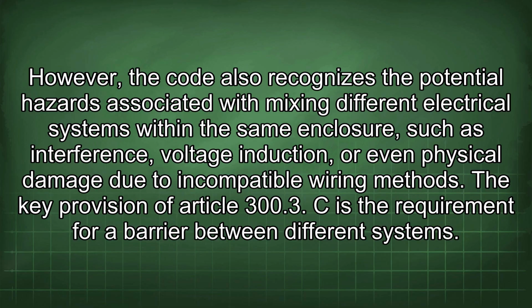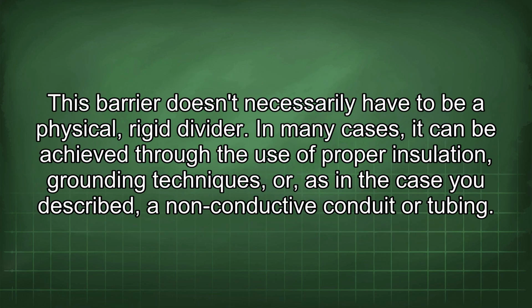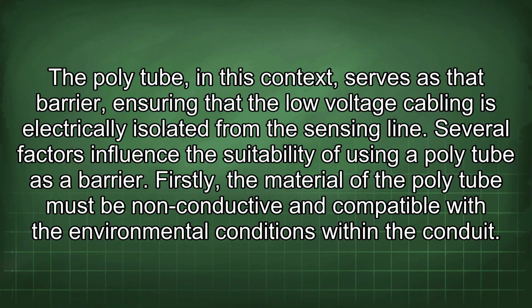The key provision of Article 300.3(C) is the requirement for a barrier between different systems. This barrier doesn't necessarily have to be a physical, rigid divider. In many cases, it can be achieved through the use of proper insulation, grounding techniques, or, as in the case you described, a non-conductive conduit or tubing. The polytube, in this context, serves as that barrier, ensuring that the low-voltage cabling is electrically isolated from the sensing line. Several factors influence the suitability of using a polytube as a barrier.